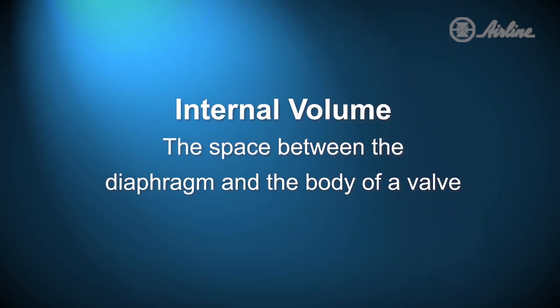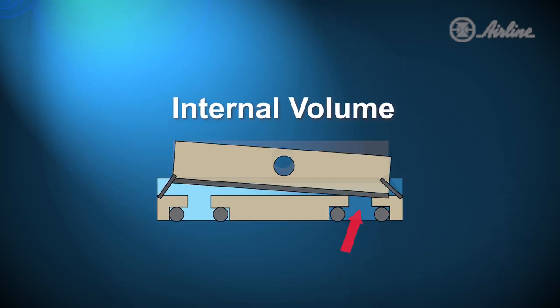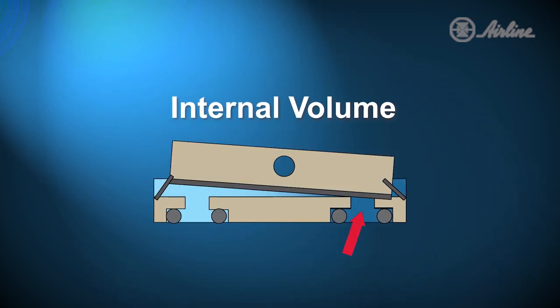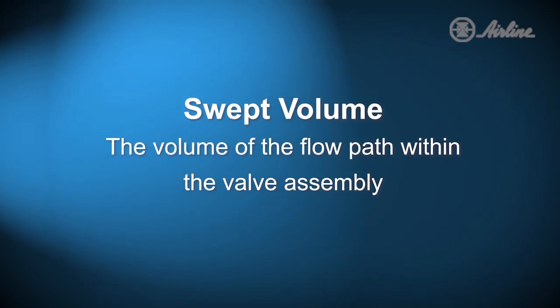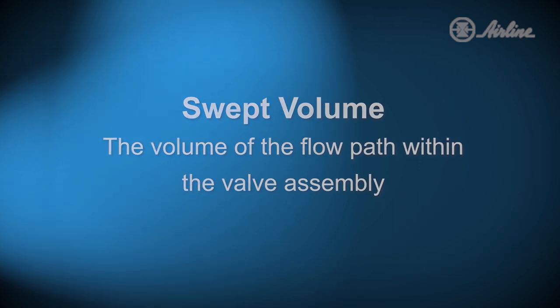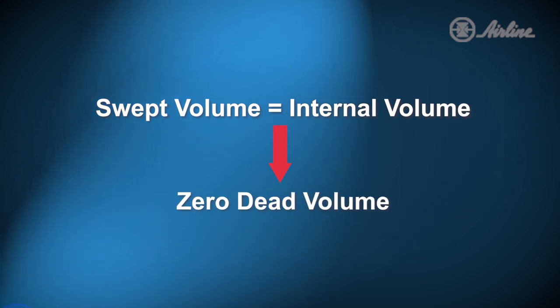The second term is internal volume — the space between the diaphragm and the body of the valve. When a valve closes, this volume becomes trapped. The third term is swept volume, which is the volume of the flow path within the valve assembly. To get a streamlined flow path, the swept volume would equal the internal volume, which in result would equal zero dead volume.